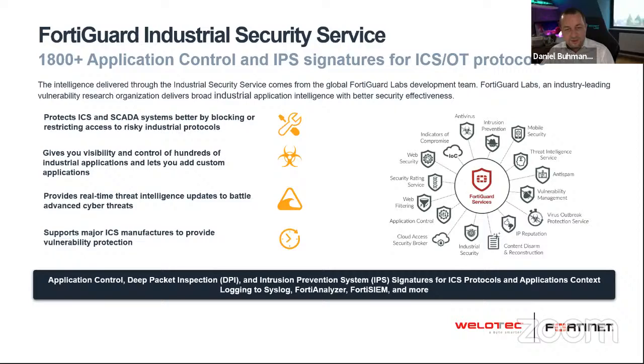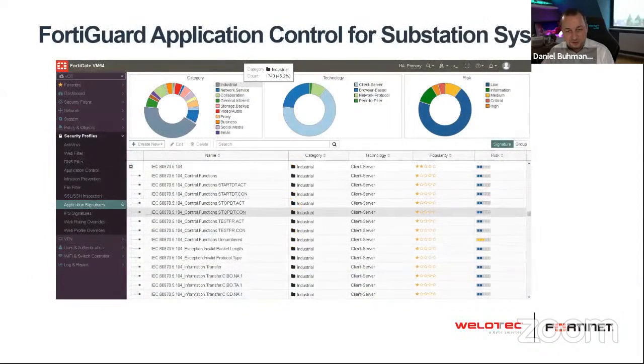One example on the next slide is a screenshot of IEC 104. In the first row of this table you'll see we recognize IEC 104. You can use this application rule to see if this package is really IEC 104, if this is really an IEC 104 message being sent, apart from just using the port. So our deep packet inspection looks into the packets and recognizes it's really IEC 104, even if it's using a different port or whatever communication there is.